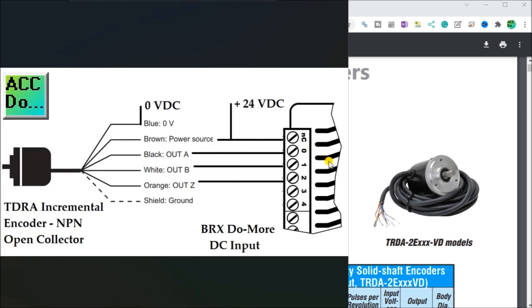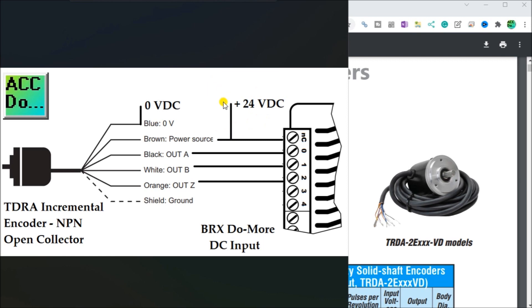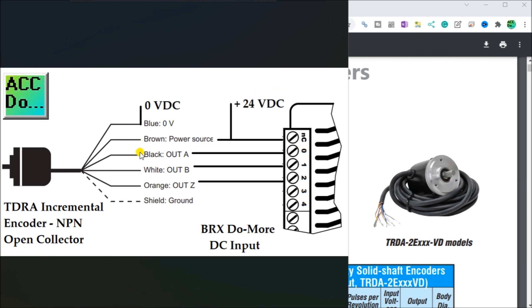Looking at the way it's going to be wired to our BRX PLC, you will see that we have our zero volts, which will be tied to the zero or the blue of our TDRA incremental encoder, which is NPN open collector. Then we have our brown wire, which is our power source, which goes to 24 volts. That's also feeding into the common of our PLC input. This is the BRX Do More DC input, so it accepts anywhere from 12 to 24 volts.